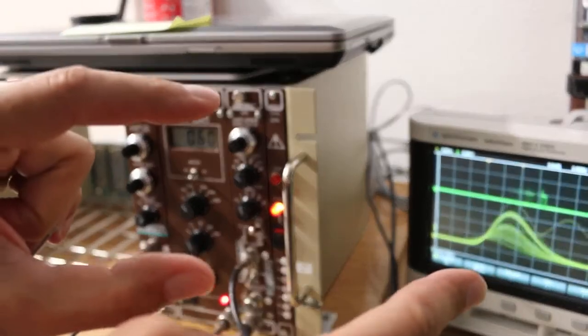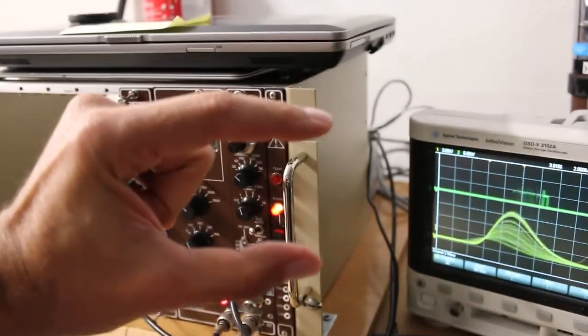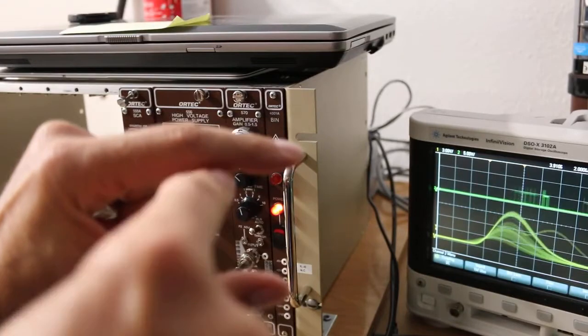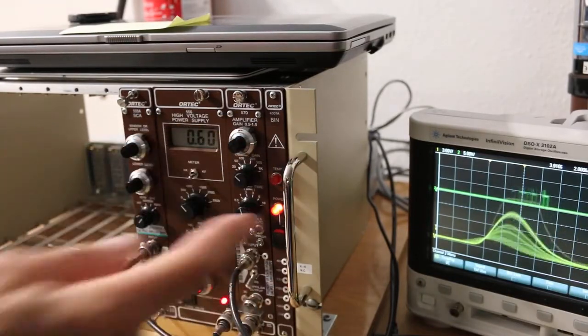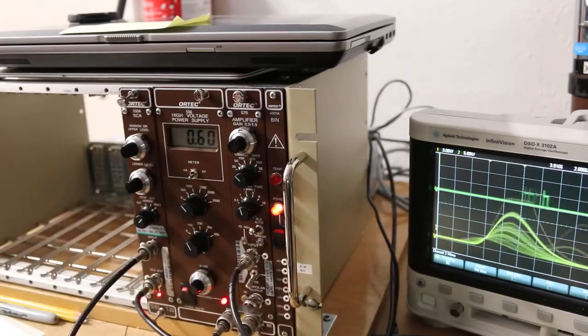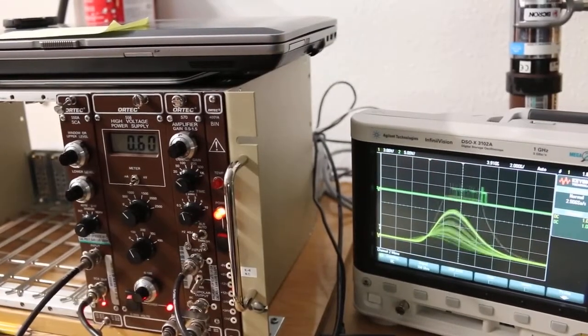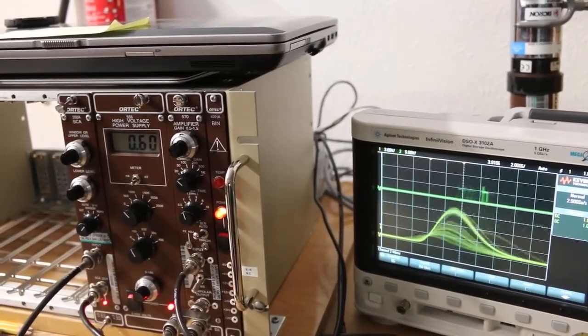And if one of those pulses you see on the oscilloscope happens to come in here and cross between the lower and upper level and go down again, if it gets in this region here, the SCA will put out a green 5 volt TTL pulse indicating yes, a pulse has gone between the voltage window that you set.